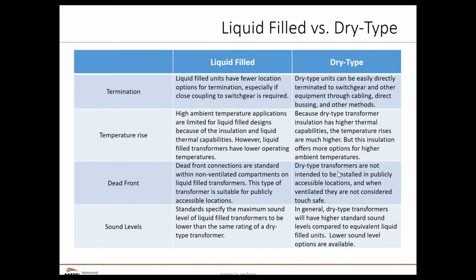Temperature rises we already addressed. We have a lot of additional temperature rise options and overload options for dry type. As a result, the kVA sizes for dry type and liquid filled may not necessarily match. I may be able to do something with a 1,000 kVA dry type transformer, 115 degree C temperature rise, which is a low temperature rise transformer, that maybe somebody specified in a 1,200 kVA liquid filled because they didn't have that low temperature rise flexibility, or as much of that flexibility with a dry type transformer.